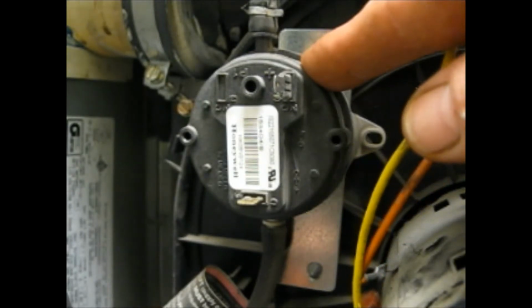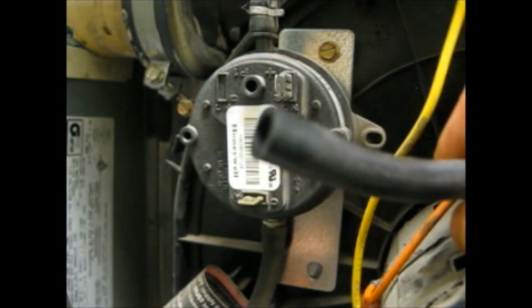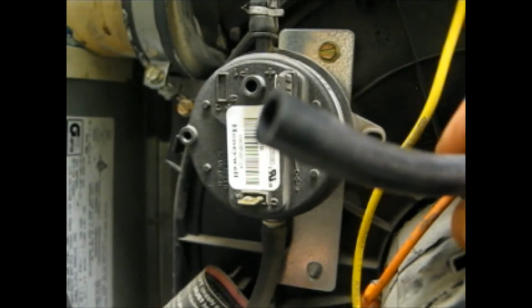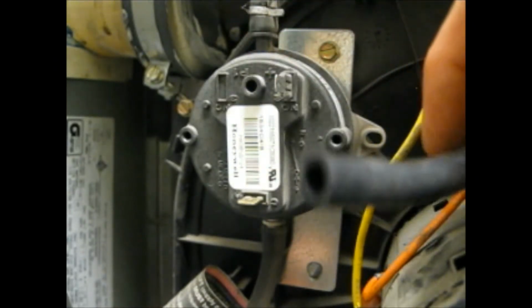from the T. To test the air pressure switch, you're going to have to take the hose you disconnected and put it in your mouth. Now, this may sound disgusting, but it's something you're going to have to do. But you want to blow very lightly. Do not blow hard. You could damage the diaphragm inside the switch.